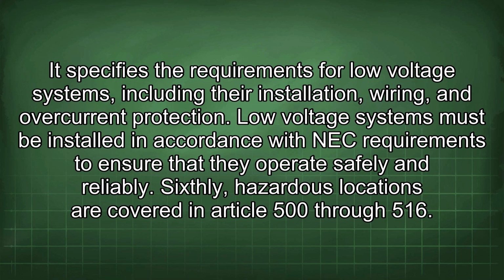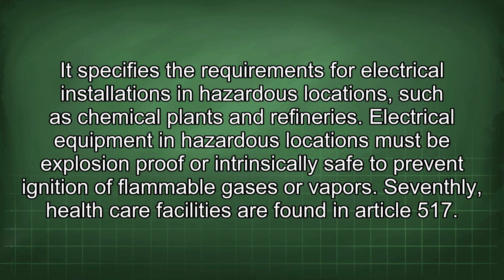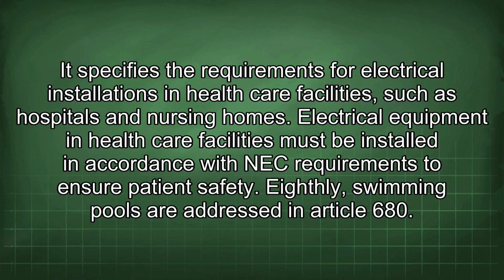Sixthly, hazardous locations are covered in Article 500 through 516. It specifies the requirements for electrical installations in hazardous locations such as chemical plants and refineries. Electrical equipment in hazardous locations must be explosion-proof or intrinsically safe to prevent ignition of flammable gases or vapors. Seventhly, healthcare facilities are found in Article 517. It specifies the requirements for electrical installations in healthcare facilities such as hospitals and nursing homes. Electrical equipment in healthcare facilities must be installed in accordance with NEC requirements to ensure patient safety.